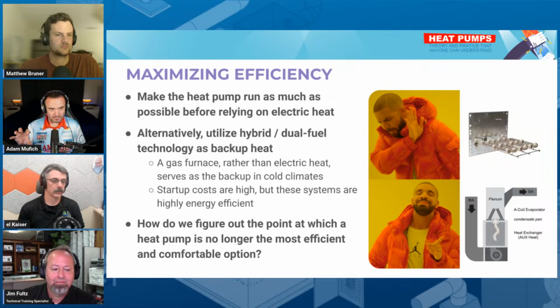You don't just hang the thermostat on the wall and flip it on and it's done. You really need to learn the individual control that you're using. And that probably comes down to, in some ways, the homeowner, right? If they're willing to have a 2 or 3 degree droop, or if they're not, they say, I want it always to be this exact temperature in my house, then you need to set that up for them to make sure that's happening.